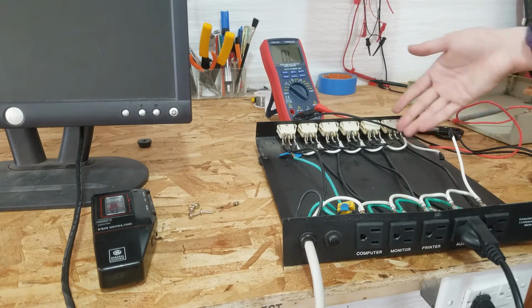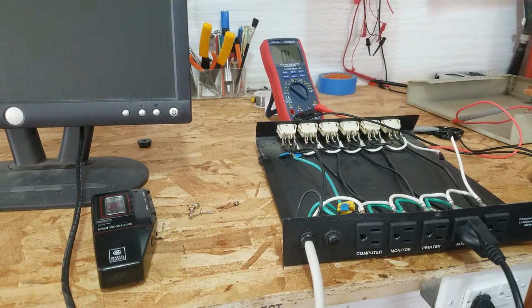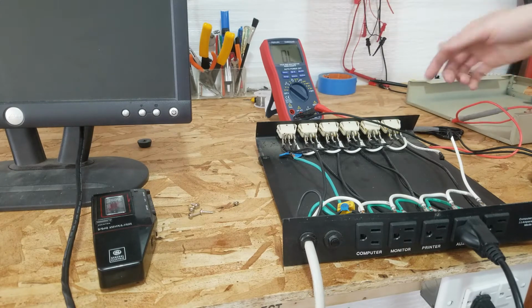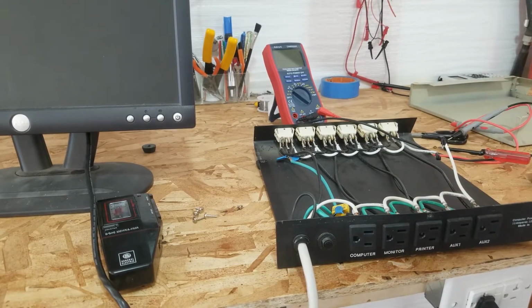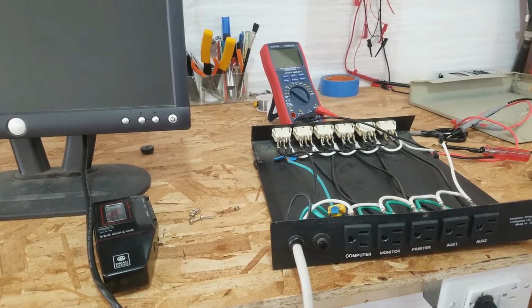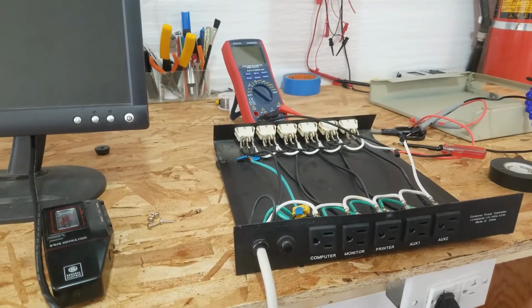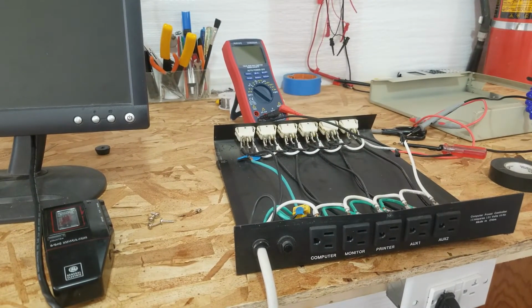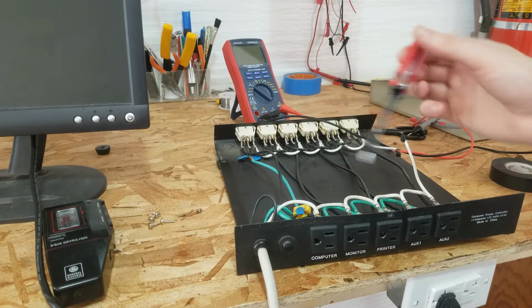So it's shorting the live to neutral, so I disconnected the neutral to all the lights. I'd rather have no lights than something shorting out. But I think that's about gonna do it for this video. So an unreliable switch light shorts out, and it shorts out the mains and trips the circuit breaker. The other worrying thing is why this circuit breaker didn't trip.